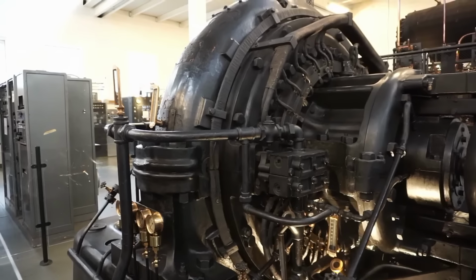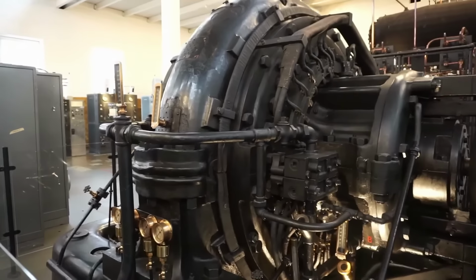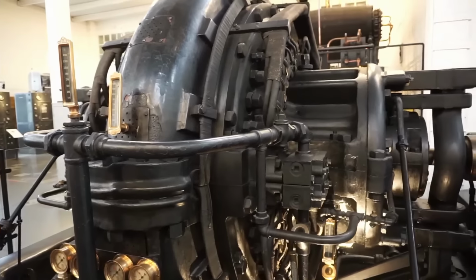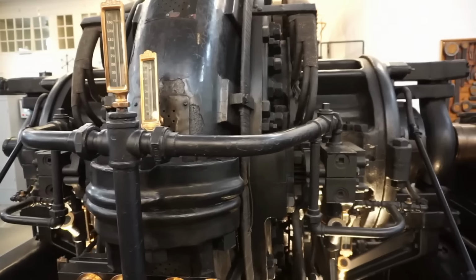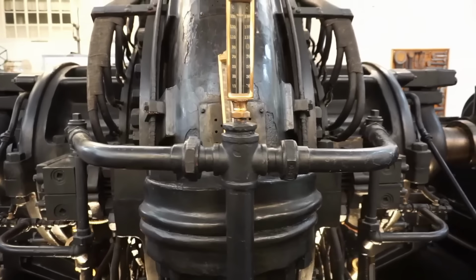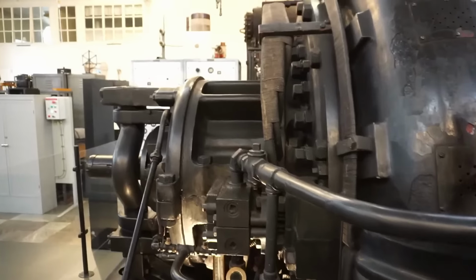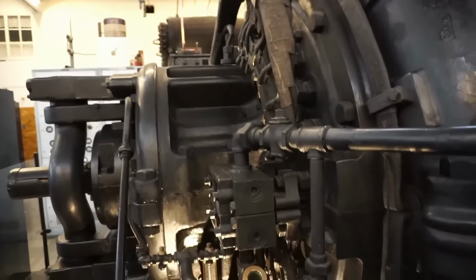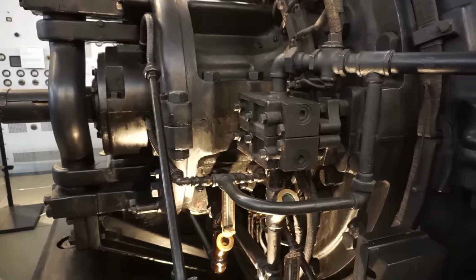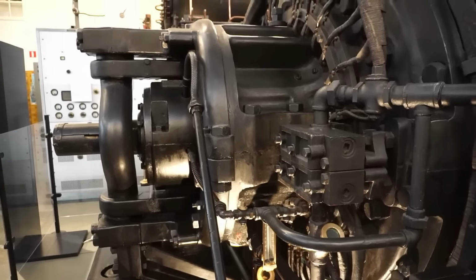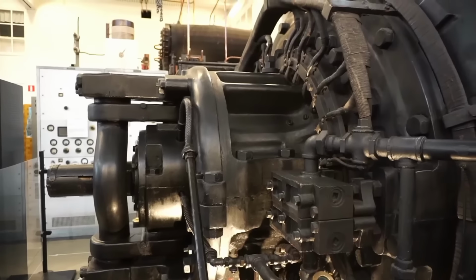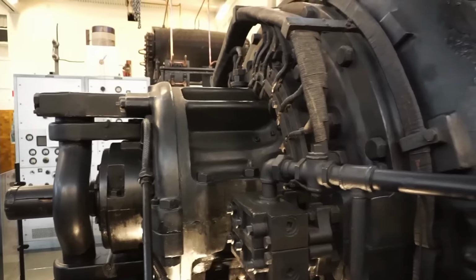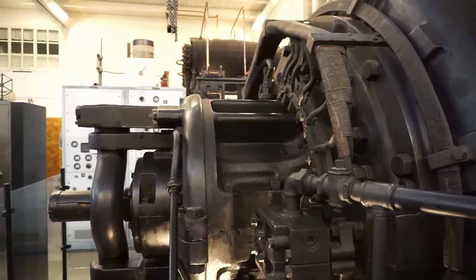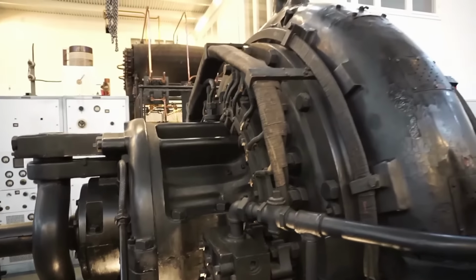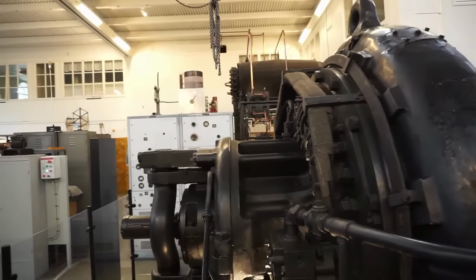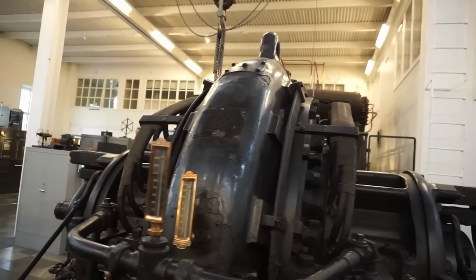This disc rotates in a magnetic field and generates 17,200 magnetic alternations per second when it's up in speed, 2,150 RPM. This magnetic alternation is picked up with 64 anchor windings and conducted up to the summing transformer in the high frequency switchgear you can see behind the alternator.